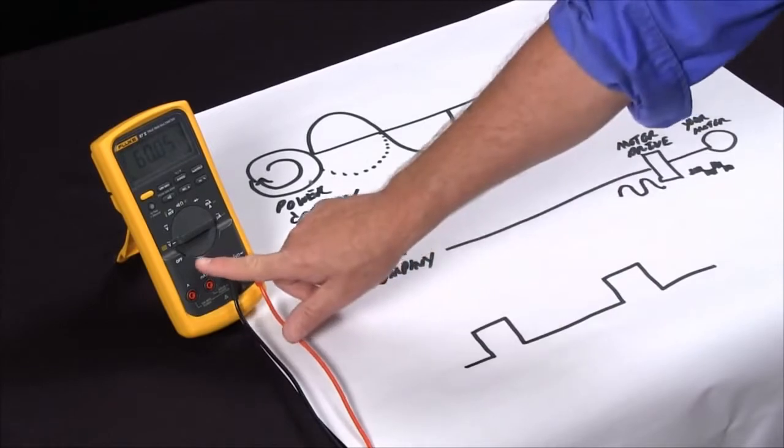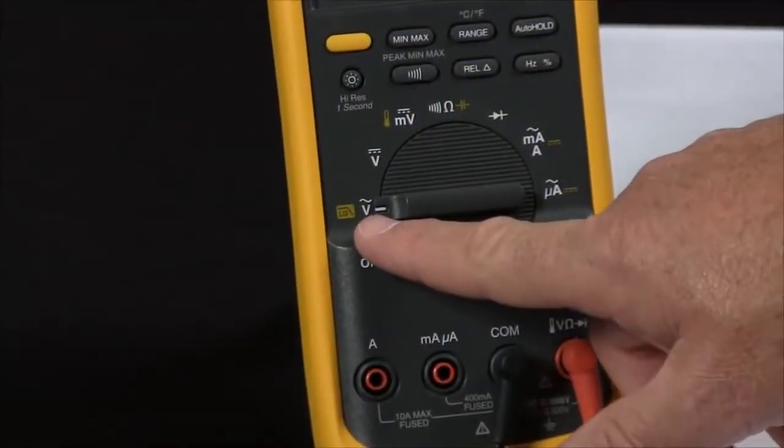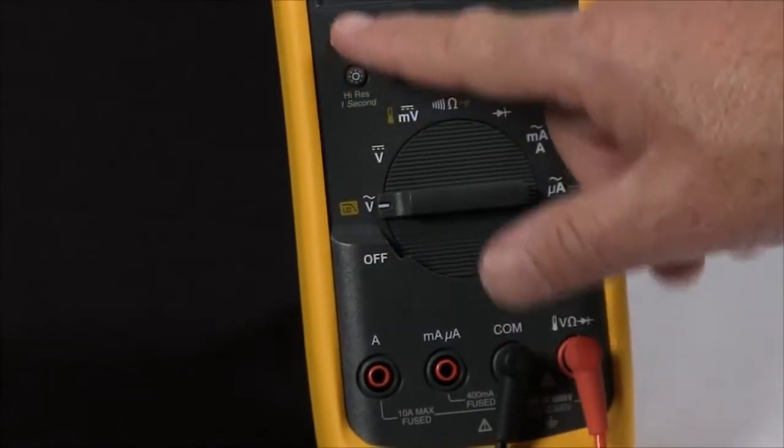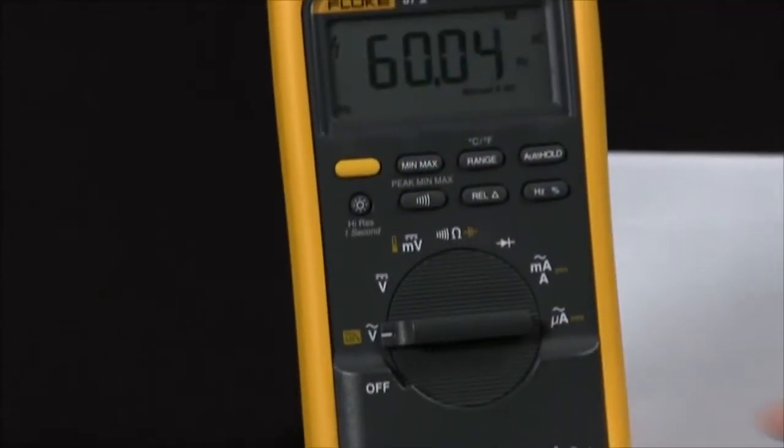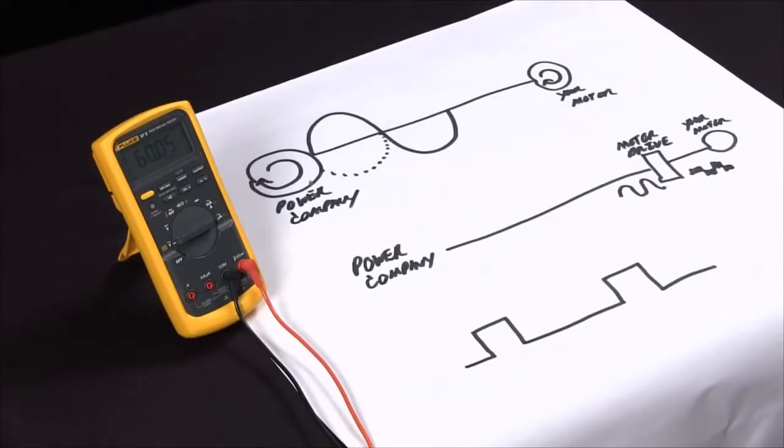We added a feature on the Fluke 87V and our 1587. If you see next to the AC volts, there's a low pass. By hitting this yellow button, what I've done is I've now converted this into a special measurement mode that will measure this pulse width modulated signal accurately, giving you the frequency.